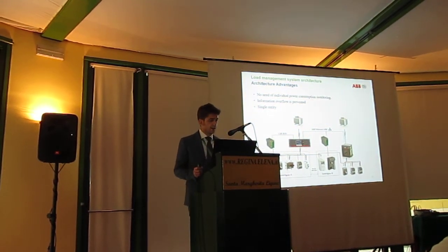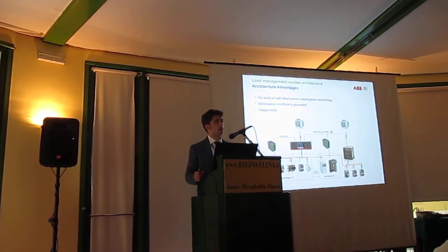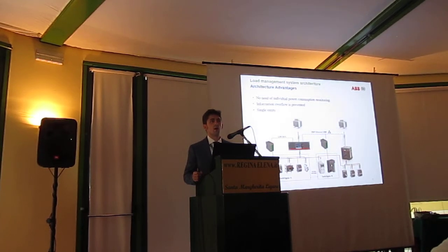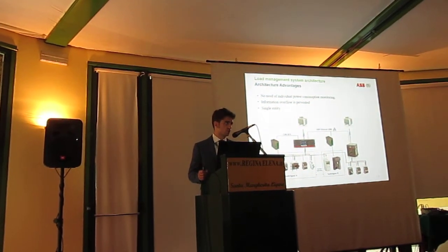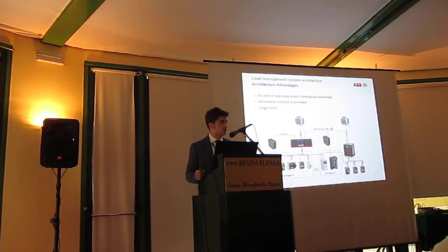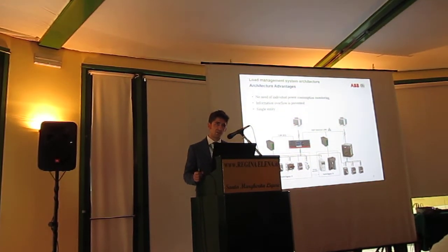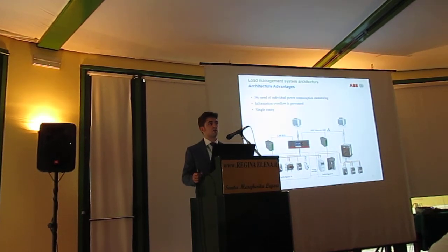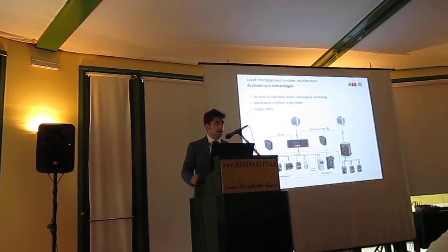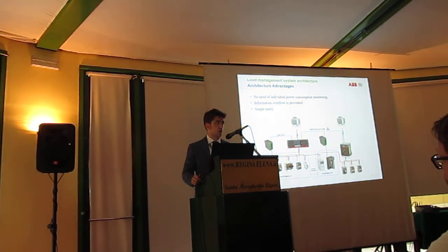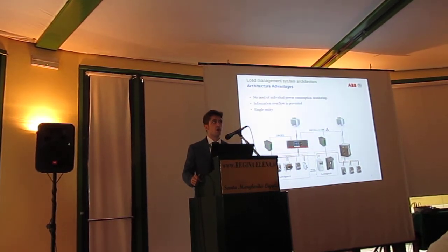To wrap up the rest of the features of the controller, I have to point out that this controller monitors the total power consumption, so there is no need to monitor individual loads. Since the controller only interacts with its downstream loads, information overflow is prevented, so we are not communicating with all parts of the power plant. Although the controller may interact with a large number of loads, it can still behave as a single entity and can communicate with a higher level controller.